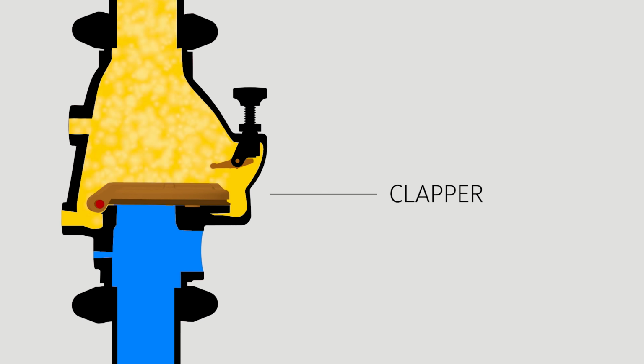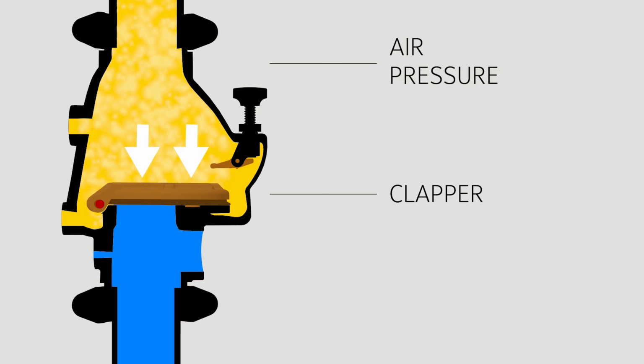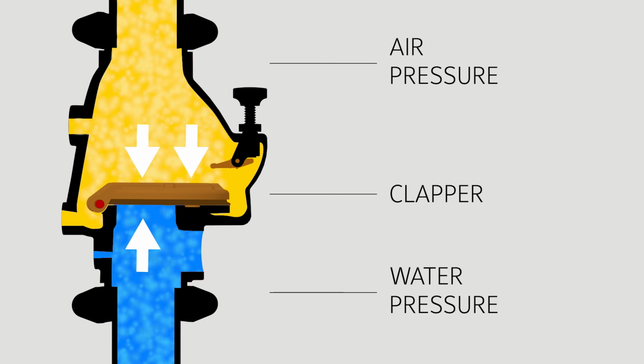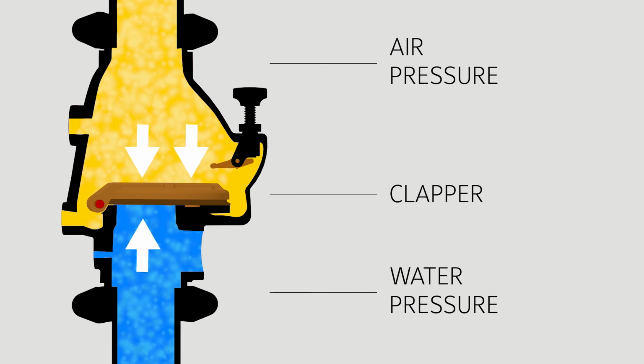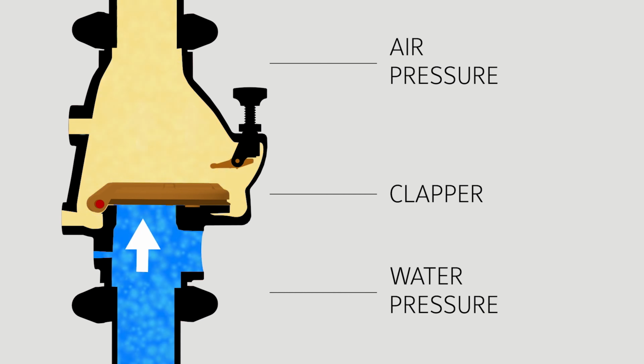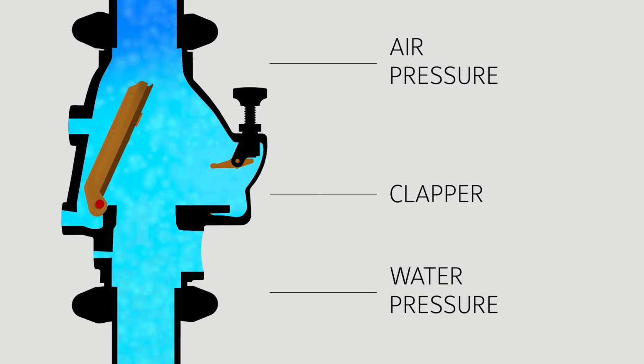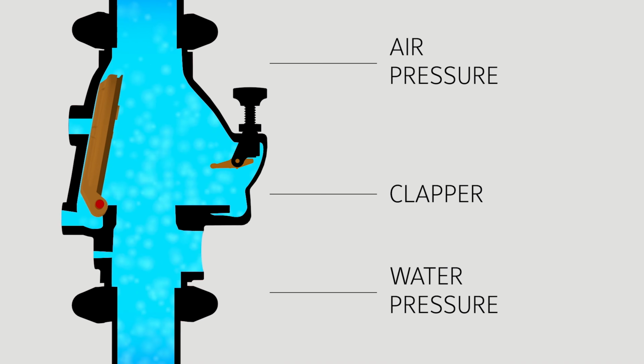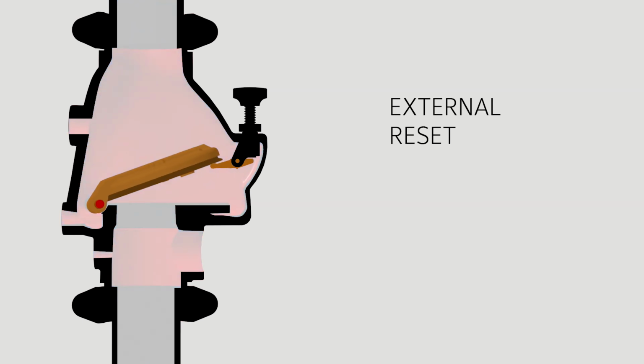The simple valve design provides greater dependability. In the ready position, air pressure in the system holds the clapper closed against the water supply pressure. When a sprinkler opens due to a fire, the pressurized air in the system is released. This allows the water to open the clapper and travel to the open sprinkler to suppress the fire. Once the fire is extinguished, the external reset simplifies maintenance.